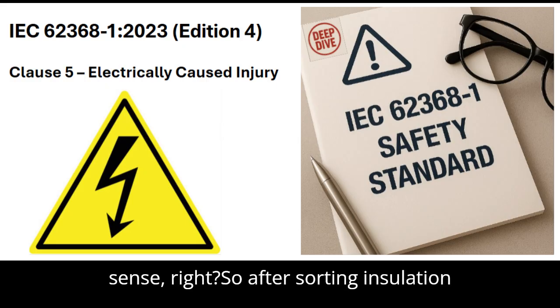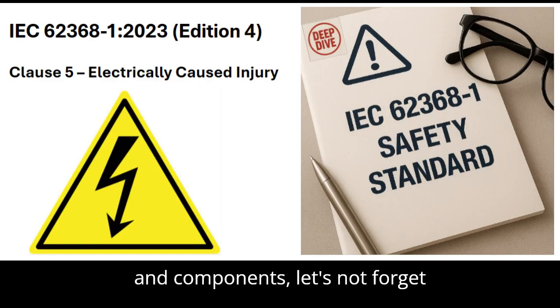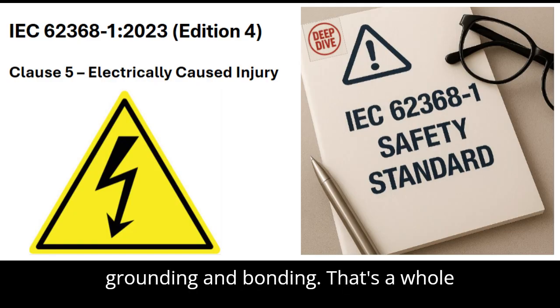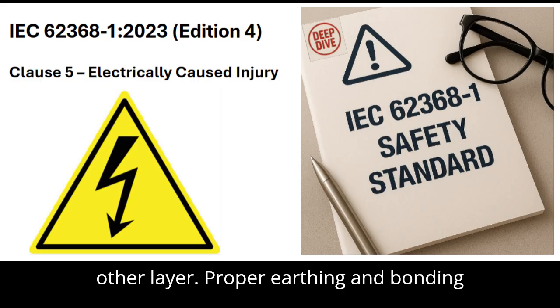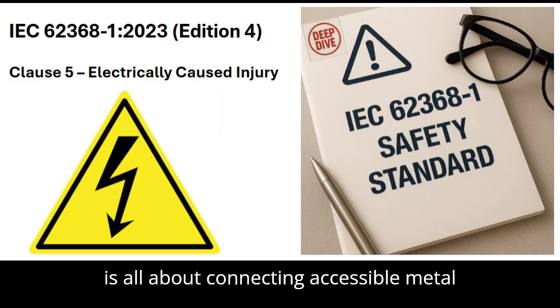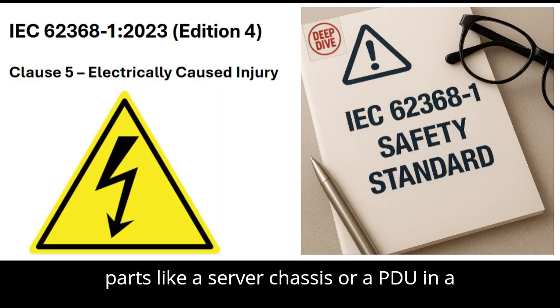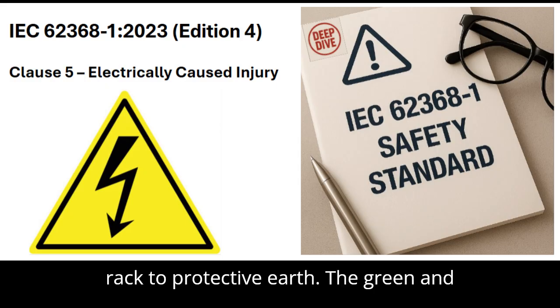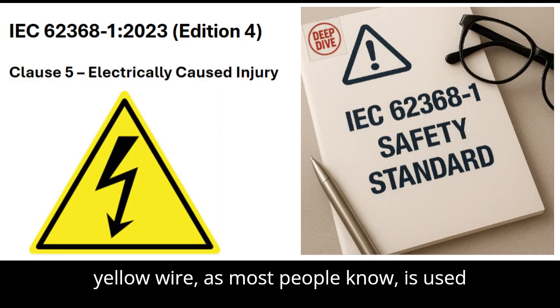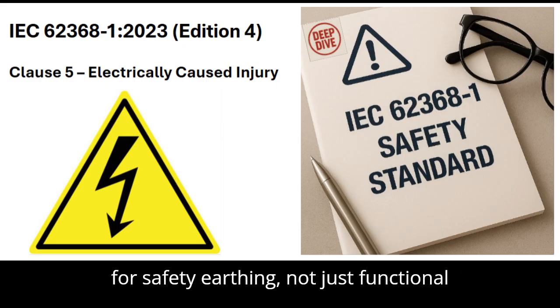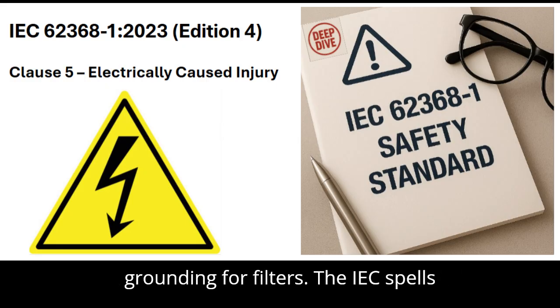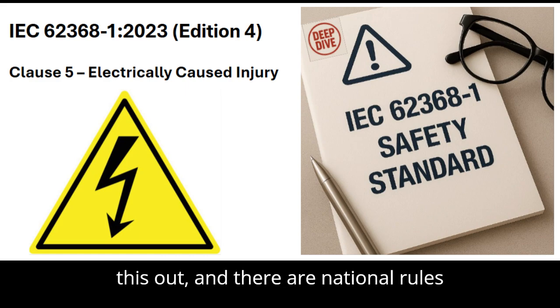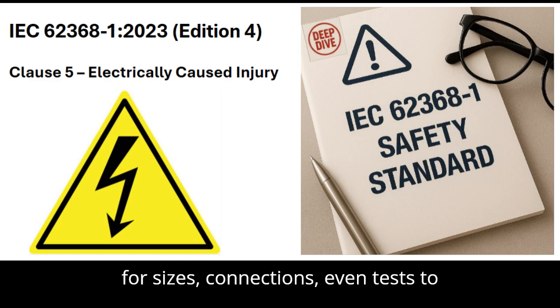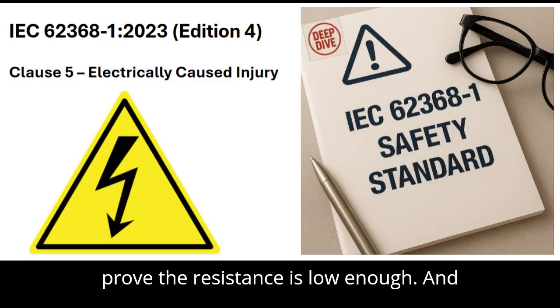Makes sense, right? So after sorting insulation and components, let's not forget grounding and bonding. That's a whole other layer. Proper earthing and bonding is all about connecting accessible metal parts, like a server chassis or PDU in a rack, to protective earth. The green and yellow wire, as most people know, is used for safety earthing, not just functional grounding for filters. The IEC spells this out, and there are national rules for sizes, connections, even tests to prove the resistance is low enough.